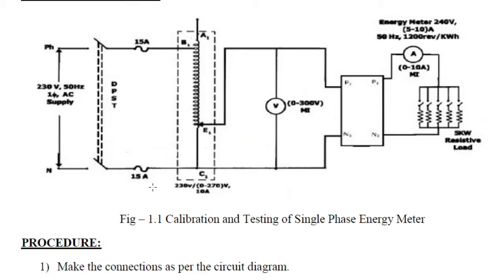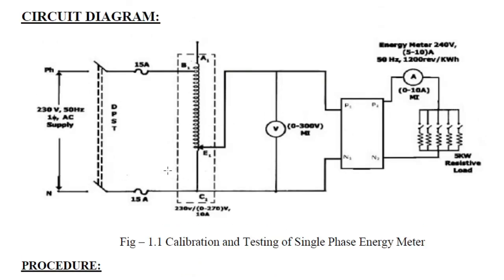Looking at the circuit diagram: a variac (auto transformer) is connected to the supply. After the variac, a voltmeter is connected to measure the supply voltage. The energy meter has four terminals — two pairs of phase and neutrals. One pair is at the source end and another pair is at the load end. P1 and N1 are the source side terminals of the energy meter; P2 and N2 are the load side terminals.